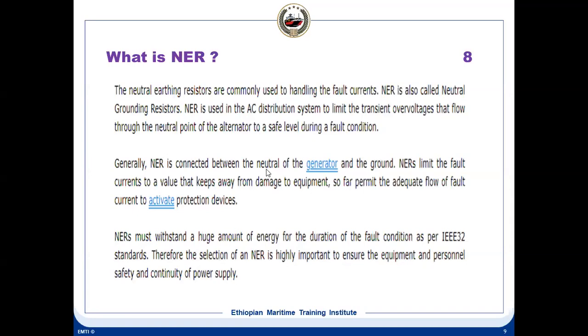So NER is connected between the neutral of the generator and the ground. It will limit the fault current to a value that keeps away damage to the equipment, while still permitting adequate flow of fault current to activate the protection devices. It must withstand a huge amount of energy for the duration of the fault conditions as per the IEEE. Therefore, selection of NER is highly important to ensure equipment and personnel safety and continuity of the power supply.